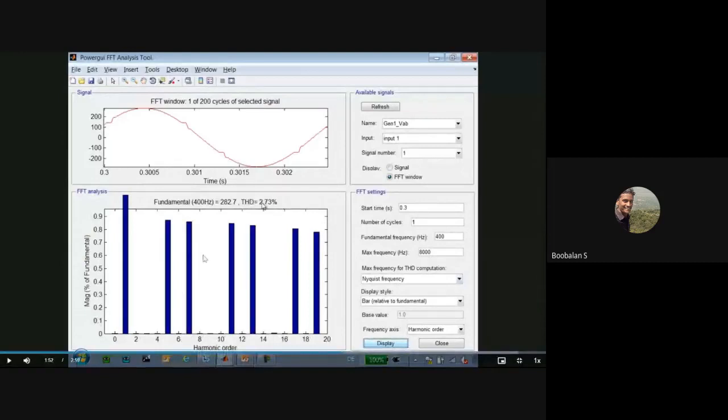So you could easily find that the total harmonic distortion is about 2.73% in the network. So in that, what is dominant if you look: 0, 1, 2, 3, 4, 5. So the first order, fifth order, seventh order, 11th order, 13th order, 17th order, 19th order. These are the frequencies present. How were these all generated? With the help of my switching devices. Depending on how the switching device operates, we could have those harmonics, right? 2.73%. And here you can see the contributions at the different orders.